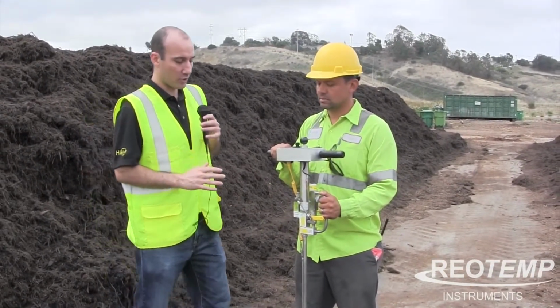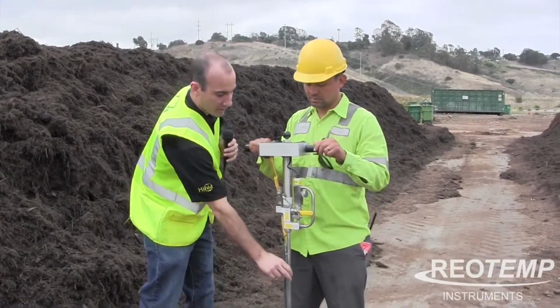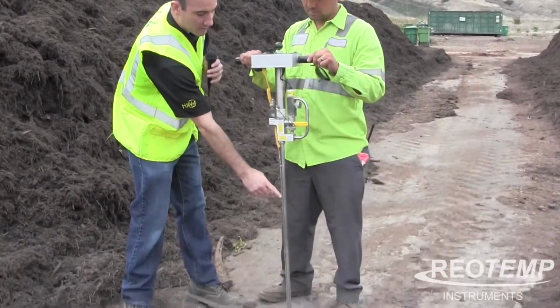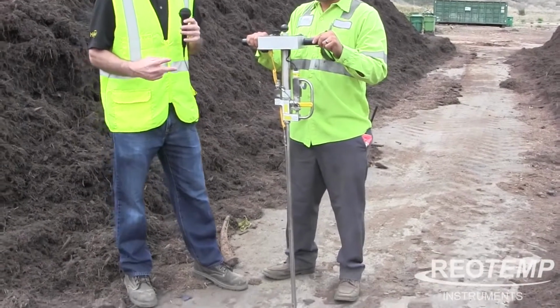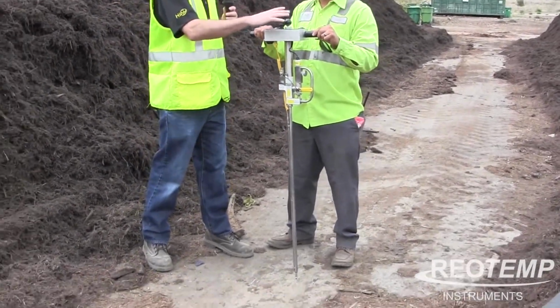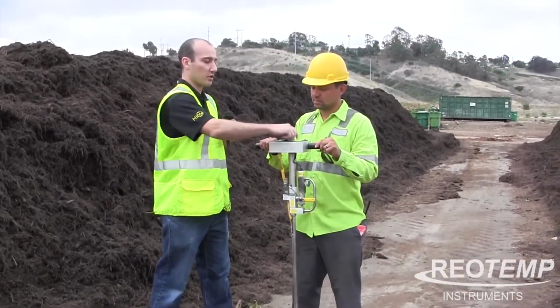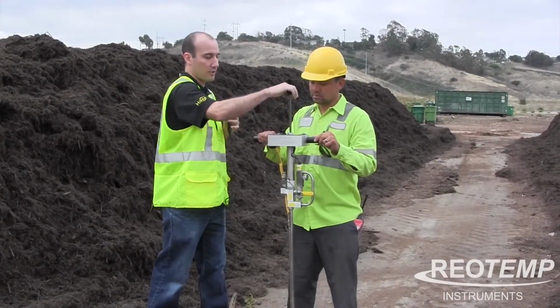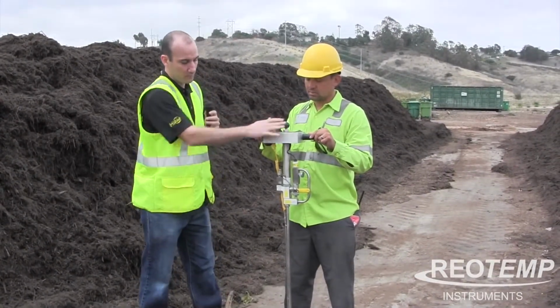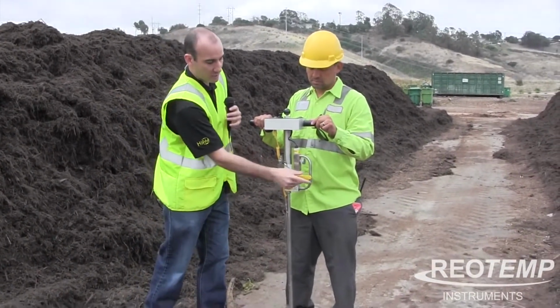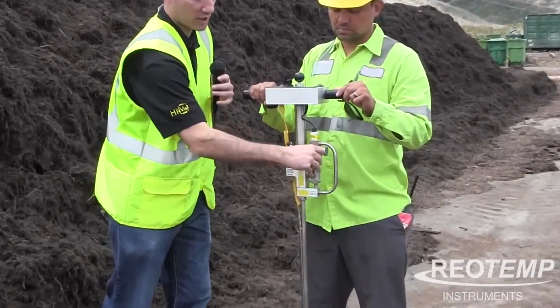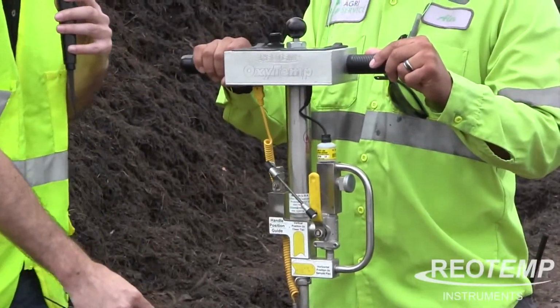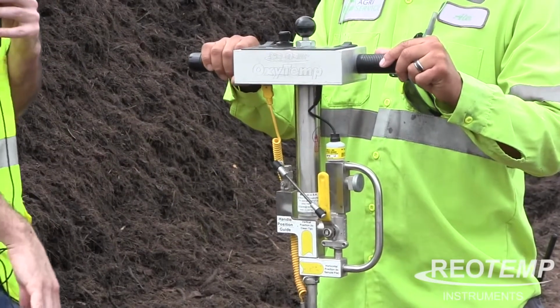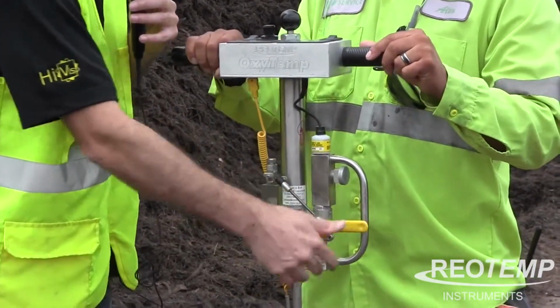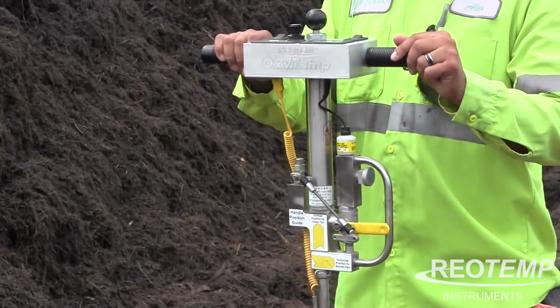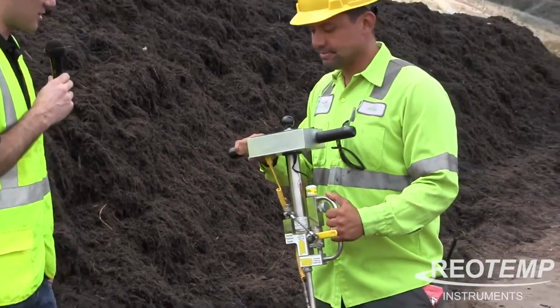So the OxyTemp probe is a combination of both an oxygen probe and a temperature probe, so you get two readings at the same time. With the oxygen sampling, you use a plunger to pull up and press down that sample. There are two positions: a sampling position and a clean out position. If it gets clogged, you can flush that clogged tip back out and go back to sampling. So with that, Alex, would you give us a demonstration?